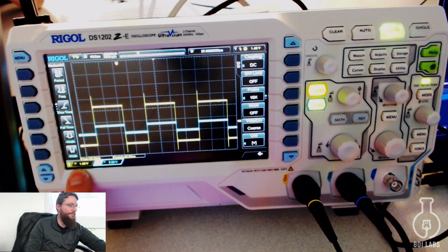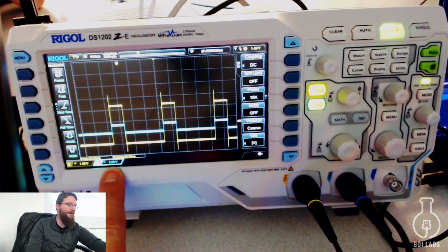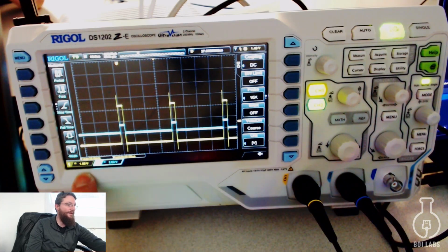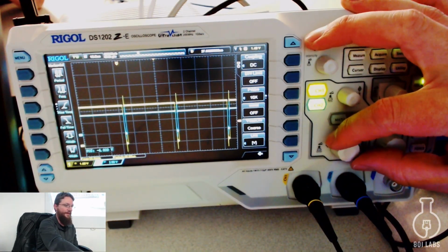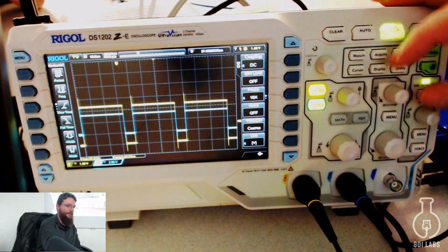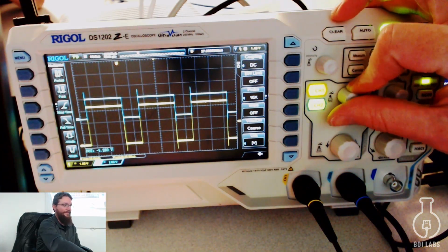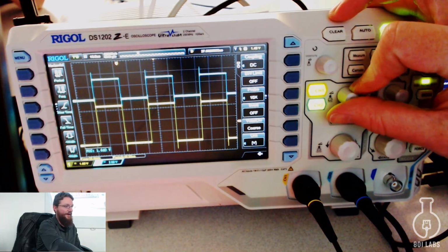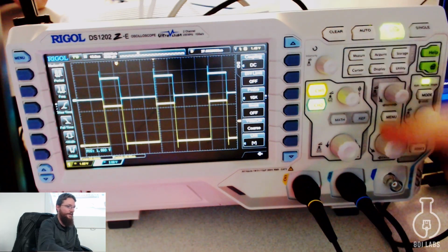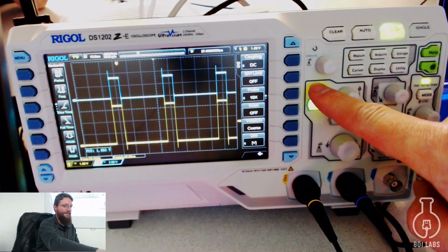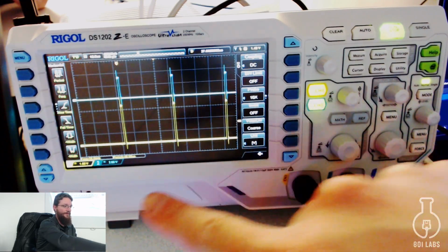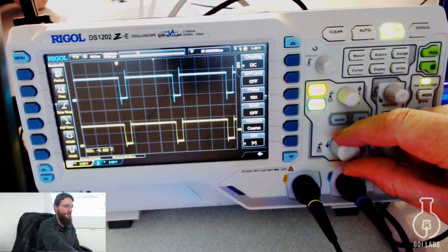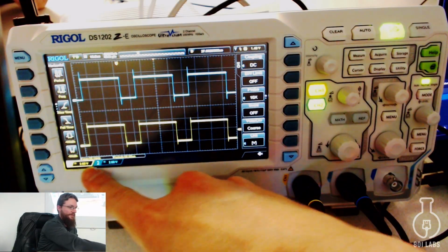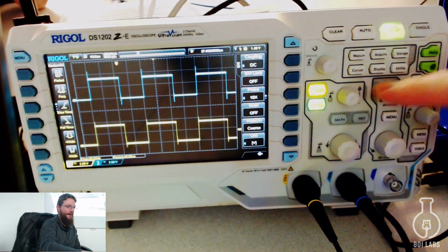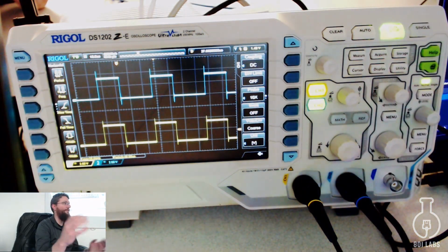If you look down here in the bottom corner, your channel 1's volts per division is 1 volt, but your channel 2's volts per division is 5 volts. And you can see 2 is highlighted and 1 is not. So when I turn this knob now, channel 2's volts per division is 2 volts. And I can turn the position knob and move channel 2 up higher, so it's aligned with that line. So whichever one is pressed last of these 2 buttons is the one you're currently controlling with these knobs. So now I've changed them both, so now they're both set to 2 volts per division, and they look the same scale now.